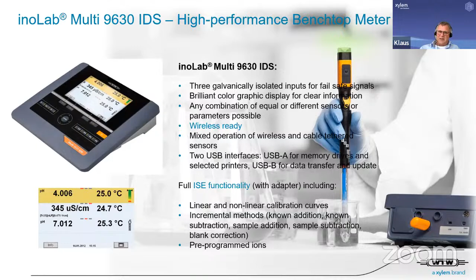Then for the big meters, that means the 9630 and 9620, we also have the full ISE functionality if desired. With a small adapter, you can connect ISE electrodes and do ISE measurements, and we have all the different possibilities available. That means linear and nonlinear calibration curves, the incremental methods, and also pre-programmed ions. So for people who also want to measure with ISE in the laboratory, it's of course possible to do this with an IDS meter. The 9620 is almost the same. We also have the ISE functionality. The only difference is that we have 2 channels instead of 3.